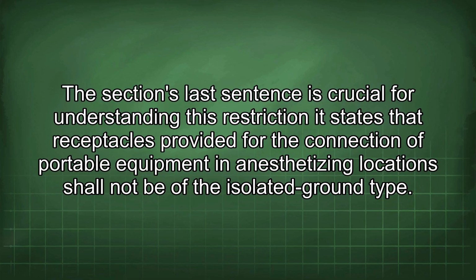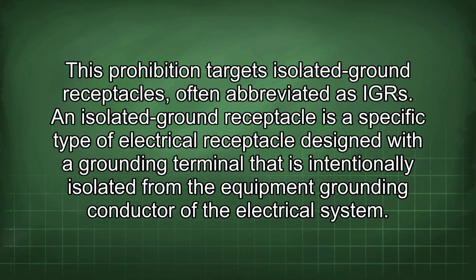It states that receptacles provided for the connection of portable equipment in anesthetizing locations shall not be of the isolated ground type. This prohibition targets isolated ground receptacles, often abbreviated as IGR. An isolated ground receptacle is a specific type of electrical receptacle designed with a grounding terminal that is intentionally isolated from the equipment grounding conductor of the electrical system.